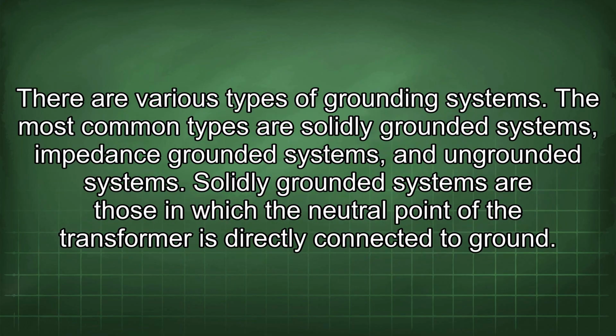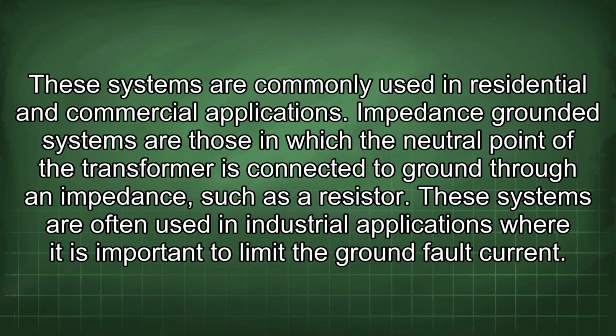There are various types of grounding systems. The most common types are solidly grounded systems, impedance grounded systems, and ungrounded systems. Solidly grounded systems are those in which the neutral point of the transformer is directly connected to ground. These systems are commonly used in residential and commercial applications.